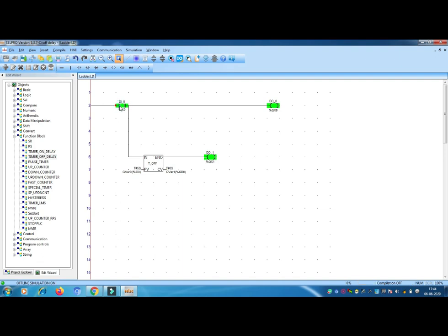But when we turn off the switch, motor 1 turns off directly, because we turn off the switch directly. After some seconds, motor 2 turns off. See, once again, when we turn on the switch, both are in on condition. When turning off the switch, motor 1 is off, but motor 2 is still running. The function of the off delay timer works only when you turn off the switch. After some seconds it will turn off, not immediately.